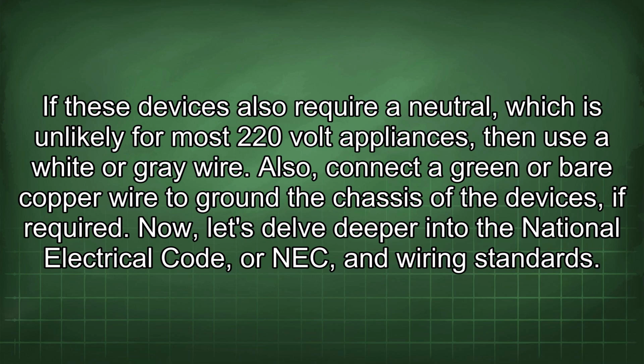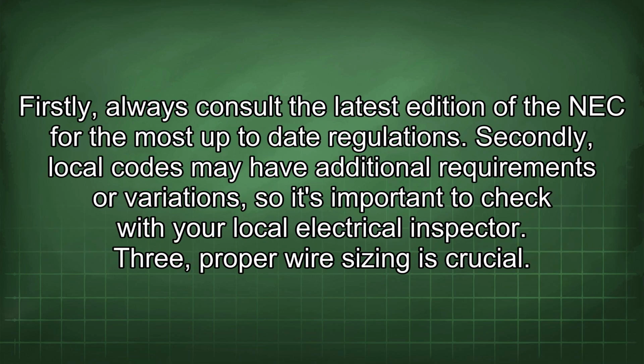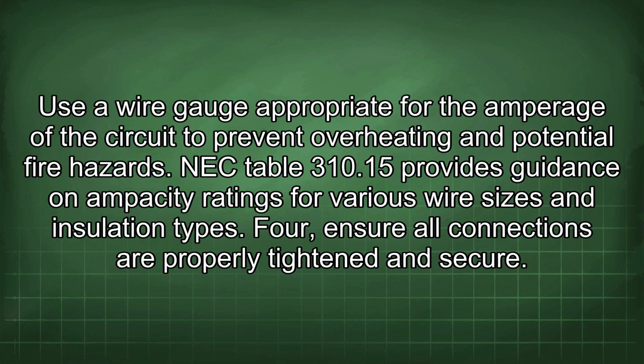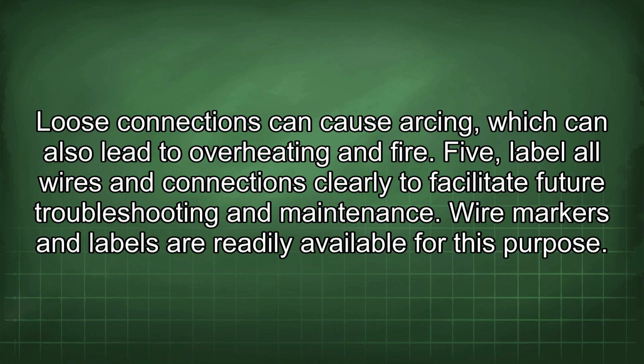Now let's delve deeper into the National Electrical Code, or NEC, and wiring standards. Firstly, always consult the latest edition of the NEC for the most up-to-date regulations. Secondly, local codes may have additional requirements or variations, so it's important to check with your local electrical inspector. 3. Proper wire sizing is crucial. Use a wire gauge appropriate for the amperage of the circuit to prevent overheating and potential fire hazards. NEC Table 310.15 provides guidance on ampacity ratings for various wire sizes and insulation types. 4. Ensure all connections are properly tightened and secure. Loose connections can cause arcing, which can also lead to overheating and fire.